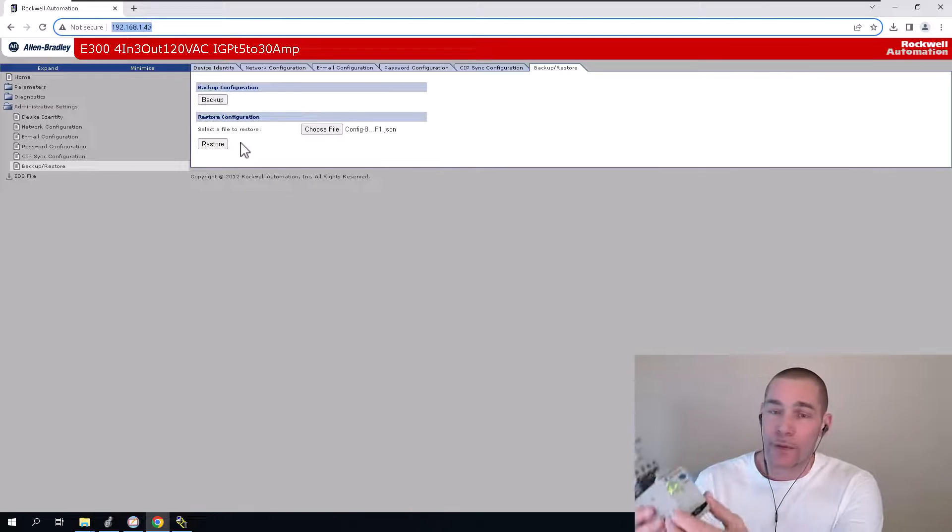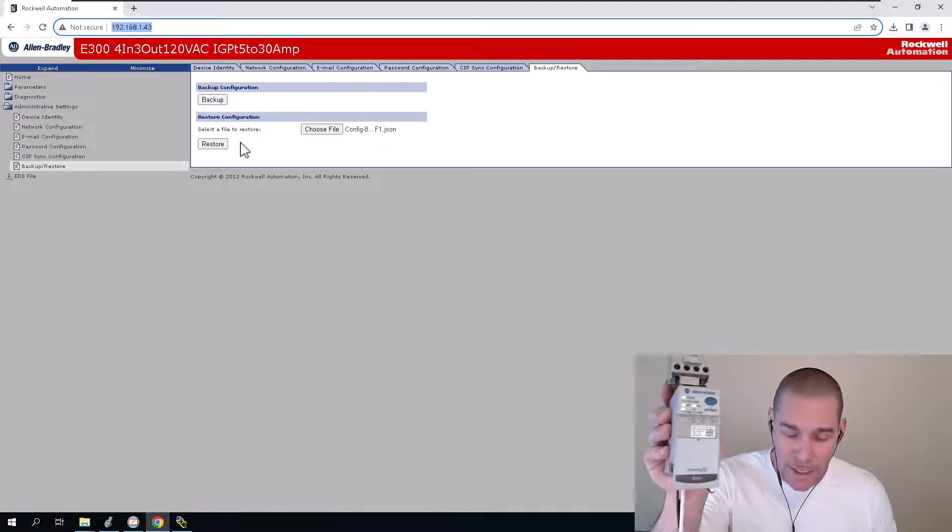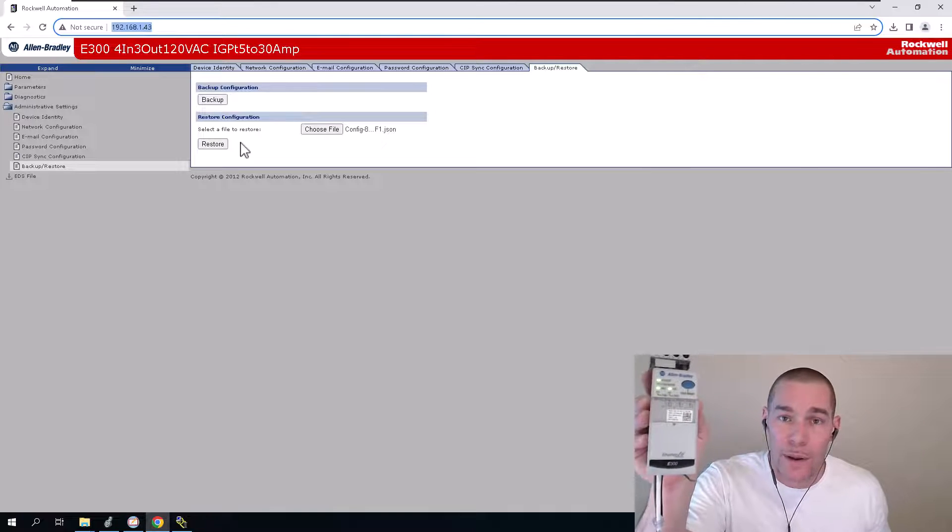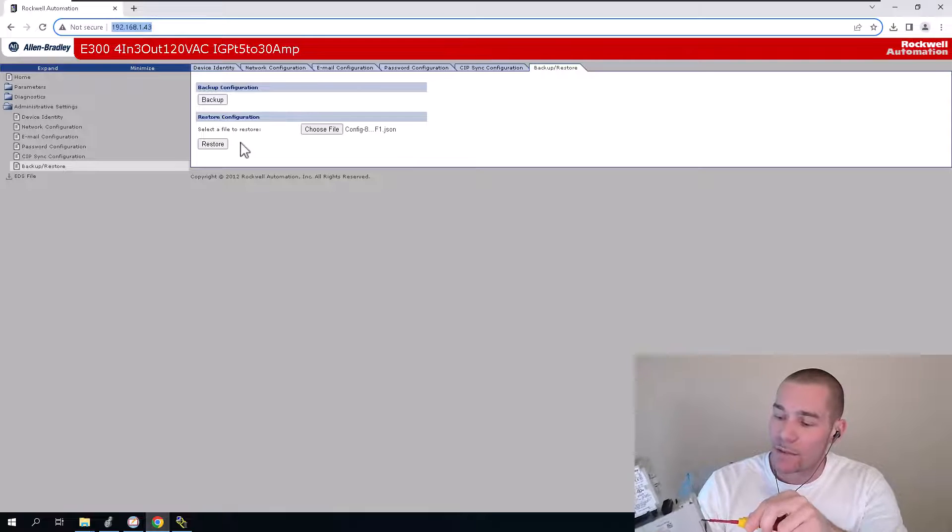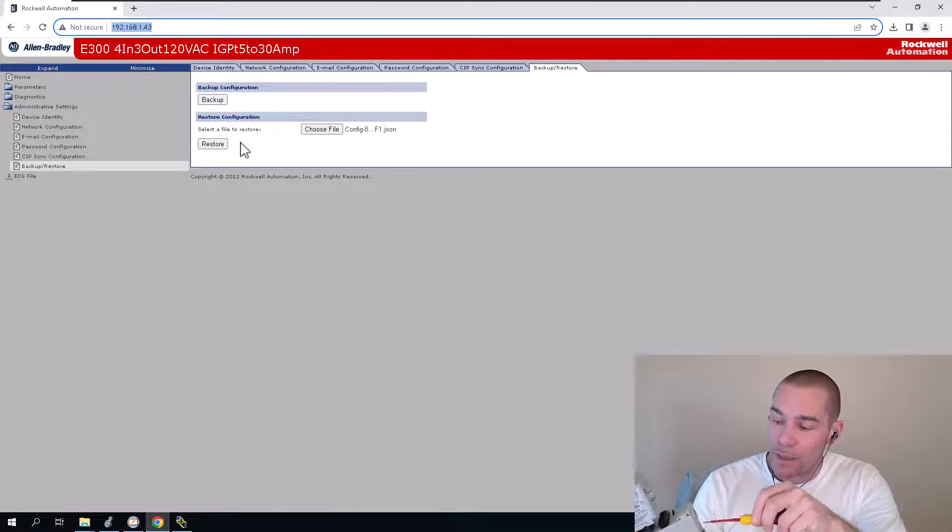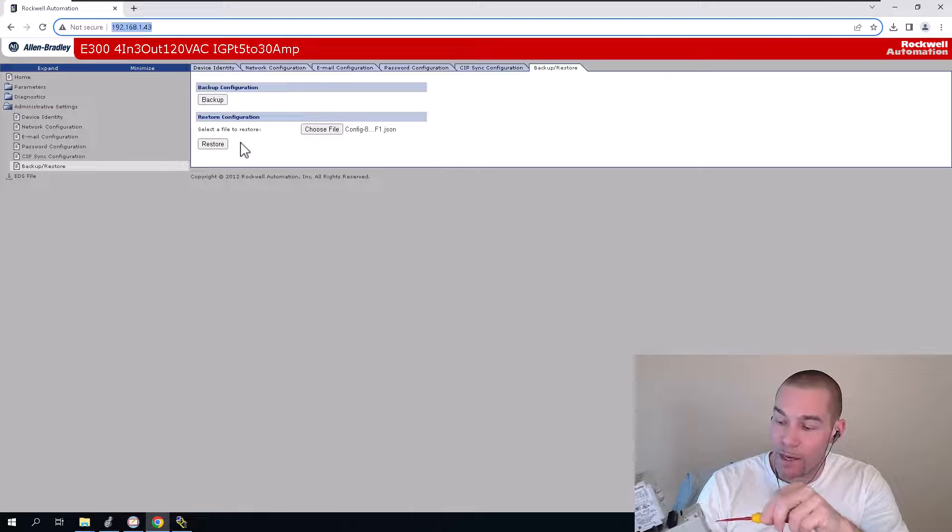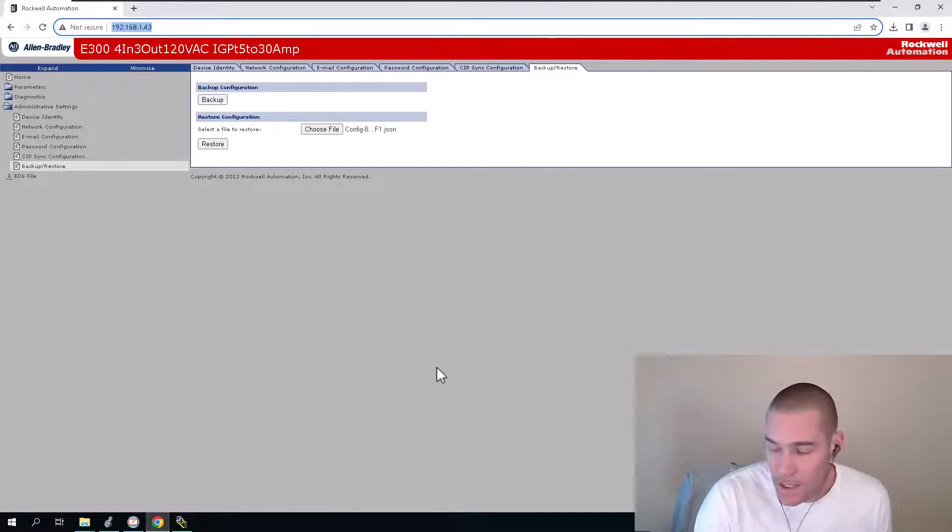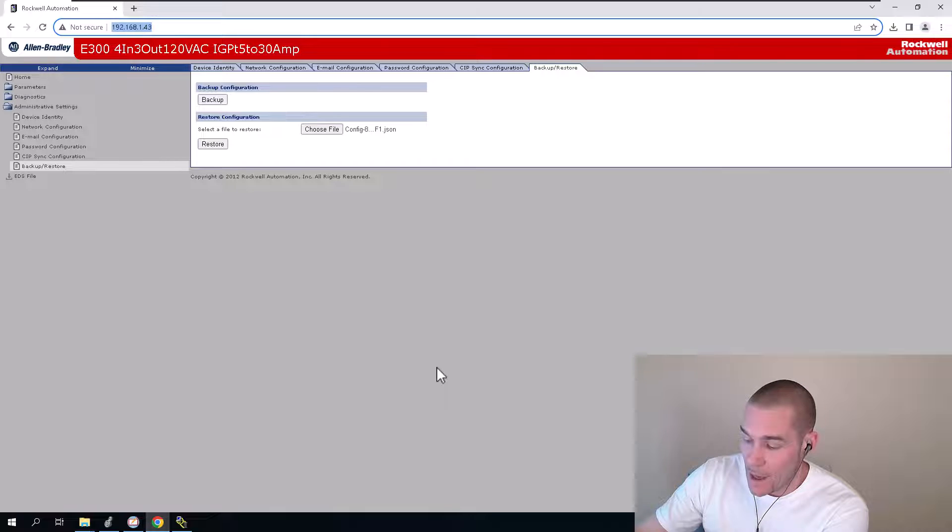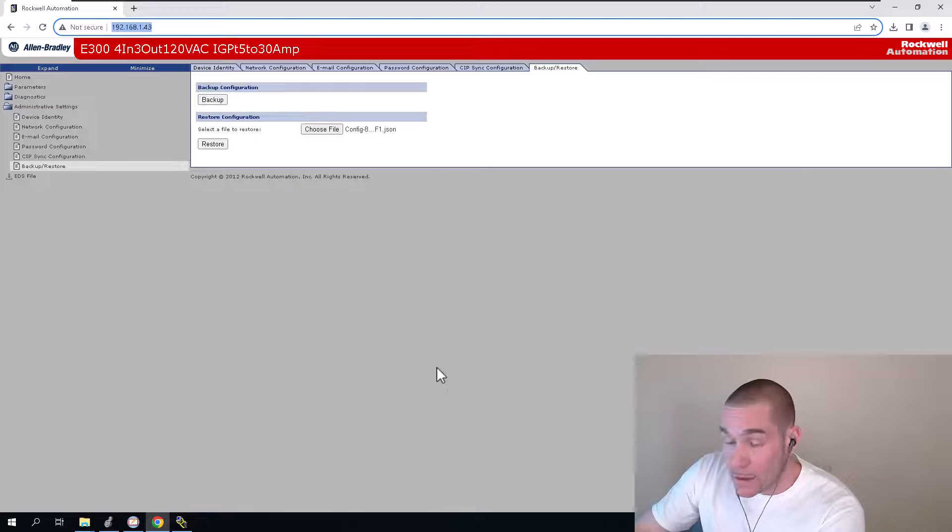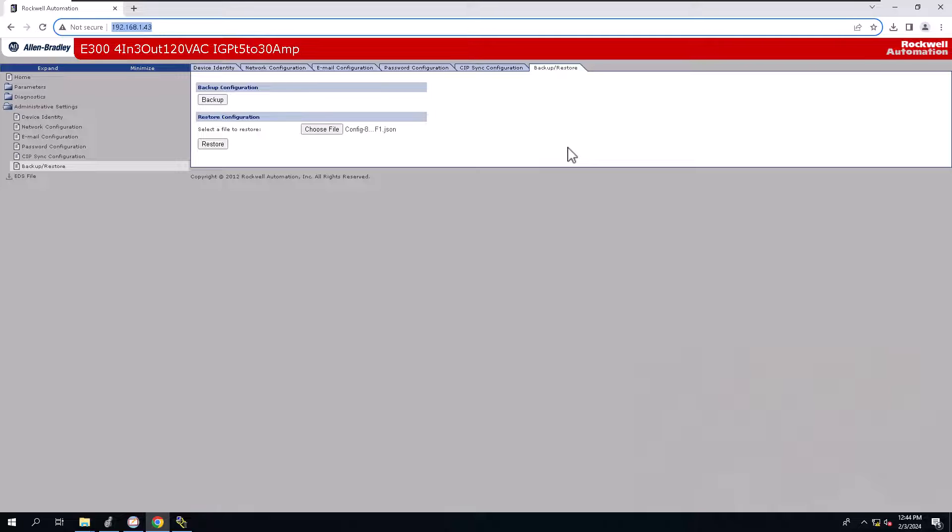So what I do for security purposes is after I get the webpage access and I get it the way I want to, I change it back to 999 because I don't want anybody going in and just being able to access the webpage at any given time or changing any of my parameters. So what I do is I go in there and I change it to 999 and then I power cycle one more time. And when I power cycle, again, why do we power cycle? We power cycle because we changed the dip switches.